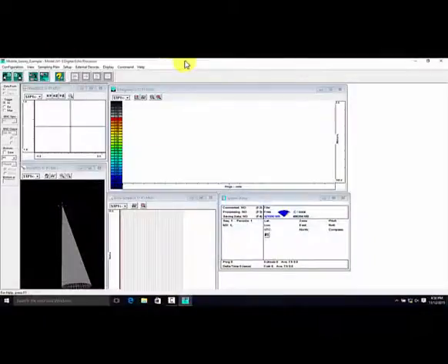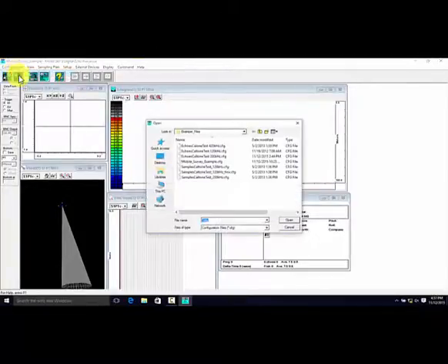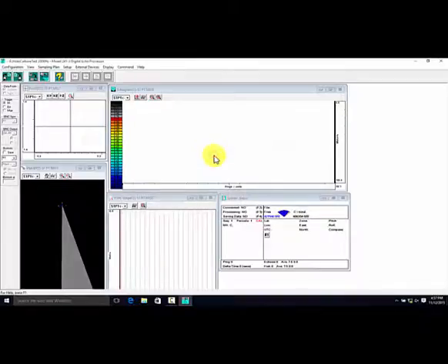Once our software is open, the first step we want to do is to open a configuration file, which contains all the settings needed to run this Caltone test. We do this by clicking configuration, open, navigating to the file that we want to use. In this case, we're going to use this Echo's Caltone test 200 kilohertz file, because as we can see on the front of our echo sounder right here, this is a 200 kilohertz echo sounder. So we open that file.